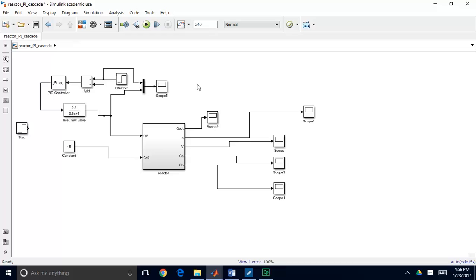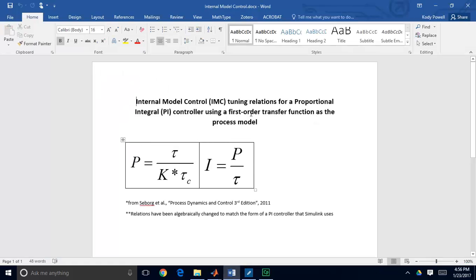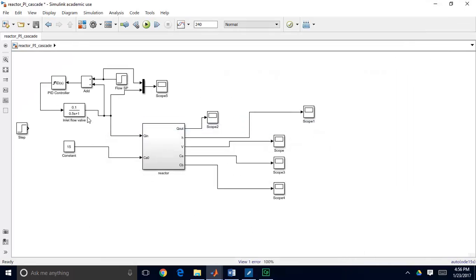What we are going to do is approximate this non-linear process by assuming it's a first order transfer function model, and then base our tuning off of that approximated model. The first thing to do is to try and get some tuning parameters. We tuned the previous process easily because we knew all of its dynamics and used IMC tuning relations. In this case we don't have the process gain or process time constant easily available, so we want to run a step test to estimate them.